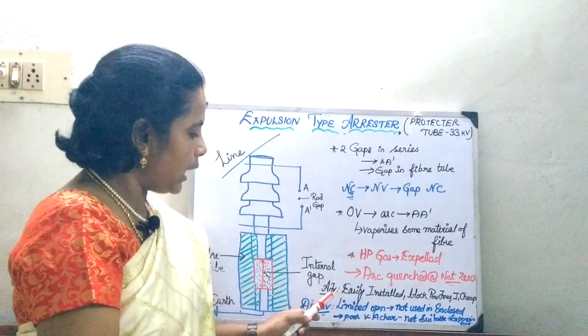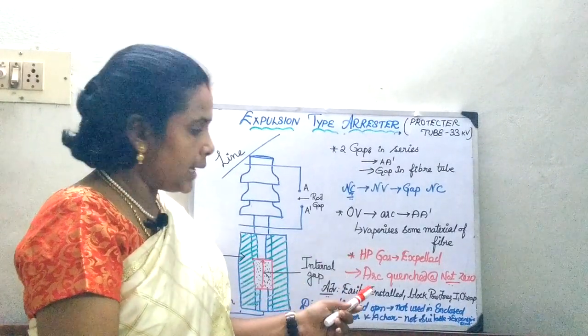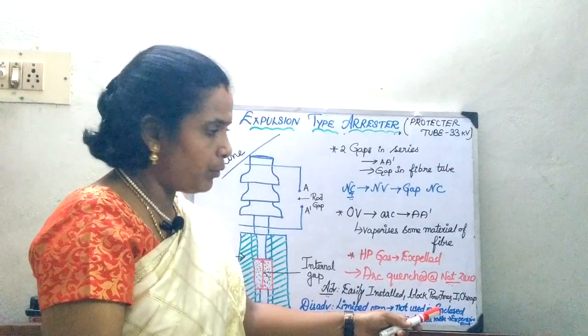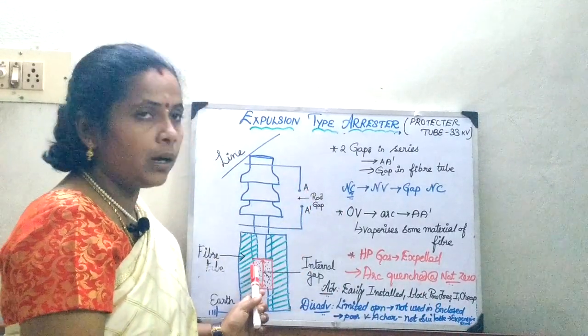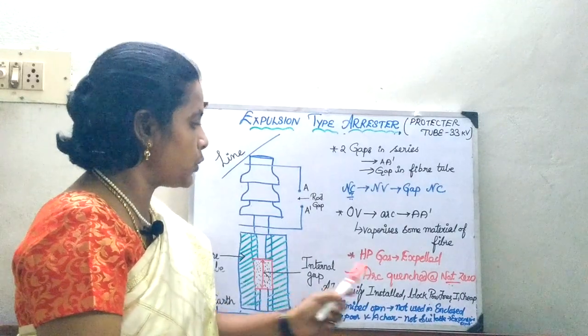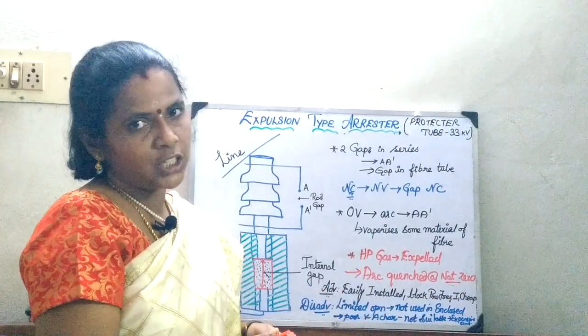The advantage is that it could be easily installed, it blocks the power frequency - that is the follow-on frequency - because you are going to have two gaps in series, that is series sparking gaps in series with each other, and it is going to be a cheaper one.